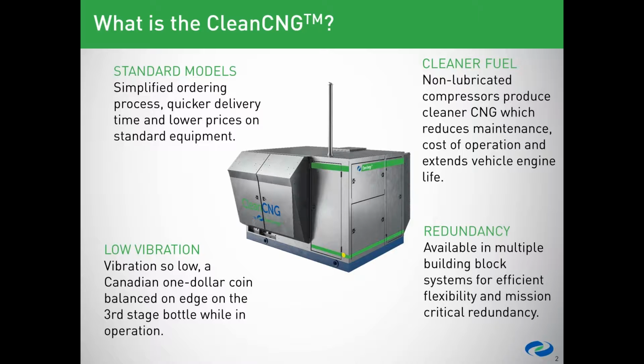This new design has much lower vibration than some of the previous models. In fact, vibration is so low that we have run several tests with a Canadian $1 coin balanced on edge on one of the scrubber bottles, and it kept standing even with the compressor running unanchored on gravel. This new design also has improved tubing and piping access, which has led to reduced interstage pressure drops, and all of these have led to lower oil carryover and cleaner gas exiting the package.